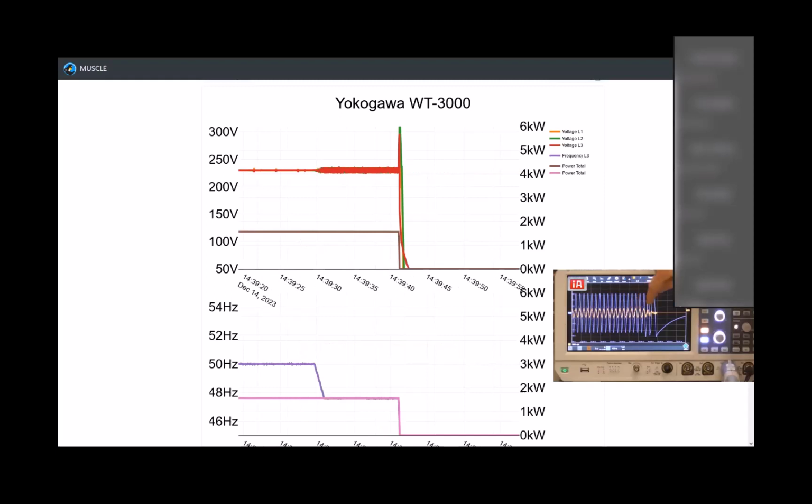And then around here was the disconnection. As you can see, I hope you can see, perhaps I can zoom in a bit, like that. At one point, the current doesn't follow the sinus signal anymore. That is where the external interface protection disconnects the system.